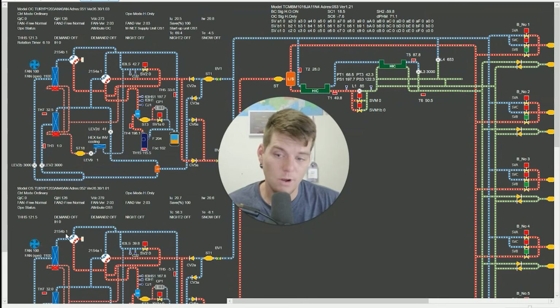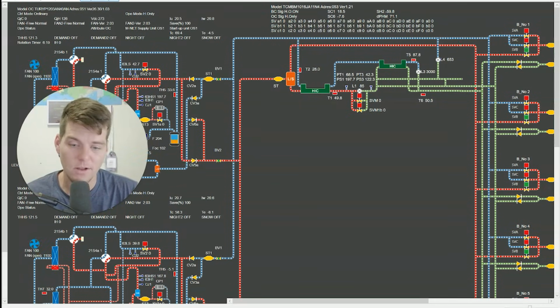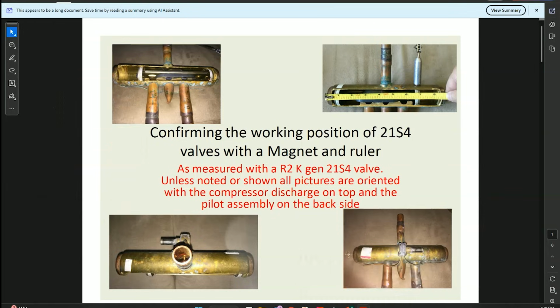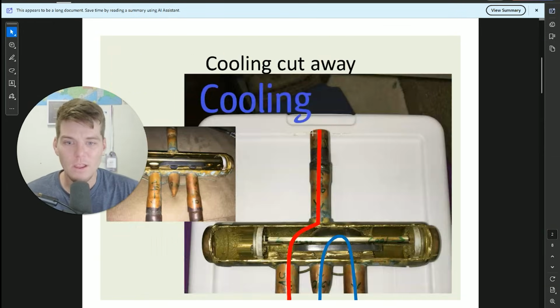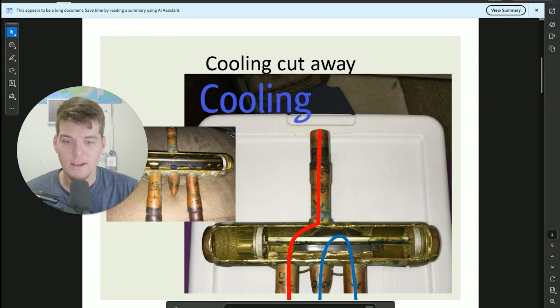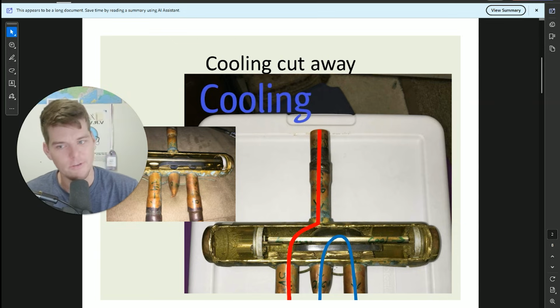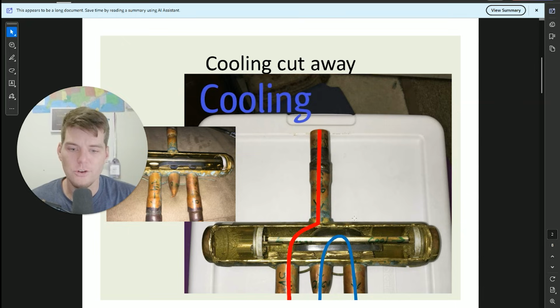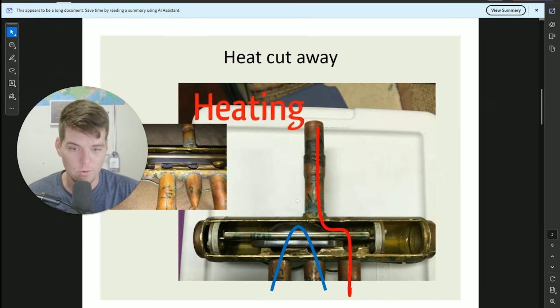Now, we think that the 21S4B four-way valve has failed. And so how do we confirm that? Well, this is how you confirm that. We take the four-way valve, right? And knowing that it's in cooling, it does this. Now, orientation matters. Am I looking at it from the left? Am I looking at it from the right? Obviously, you're going to want to take temperature measurements across the four-way valve itself or use a magnet.